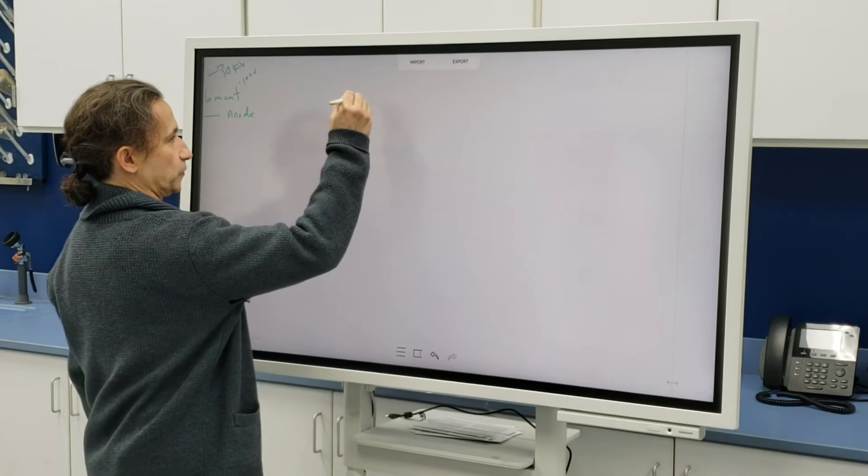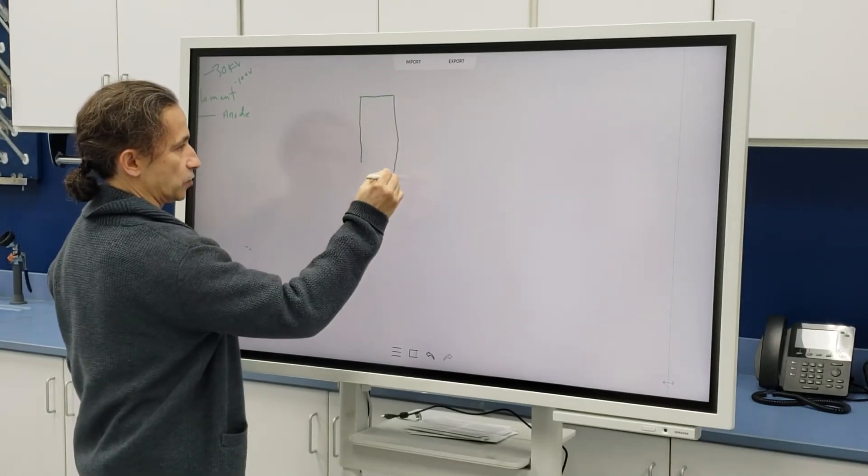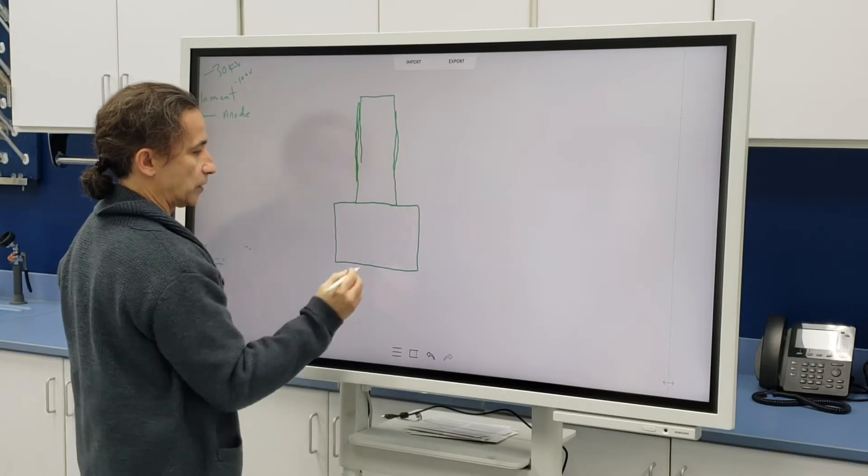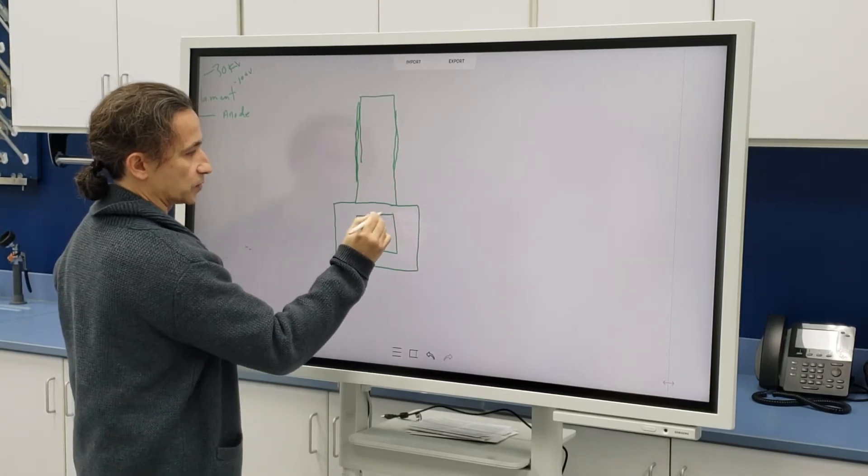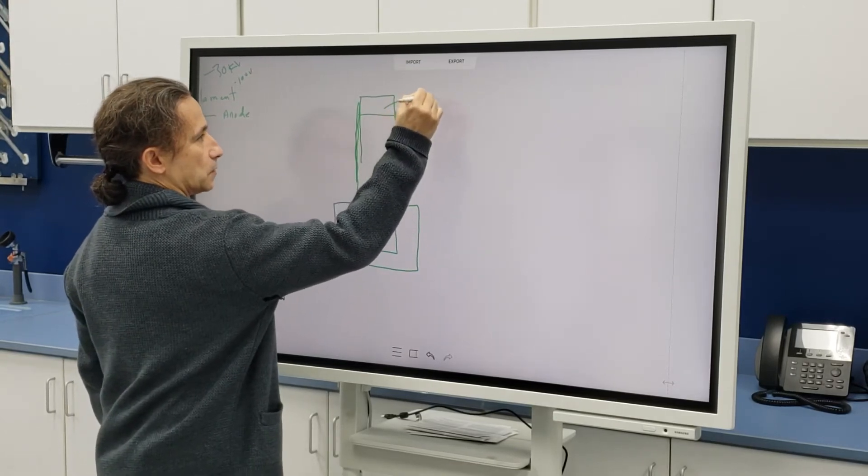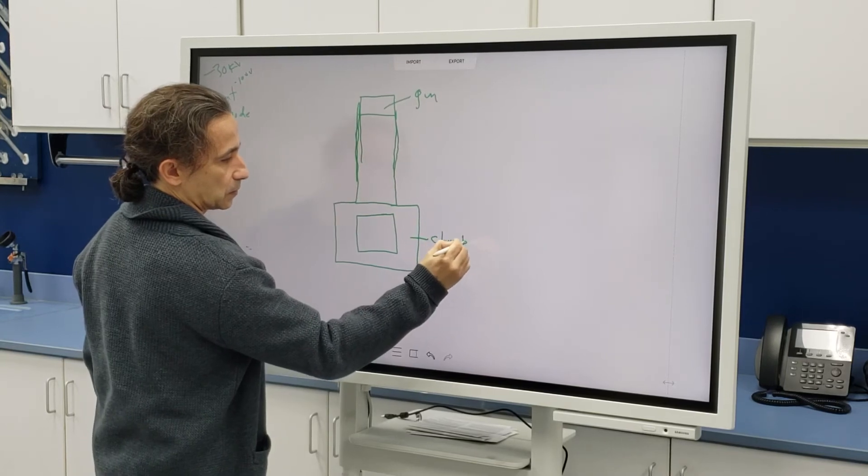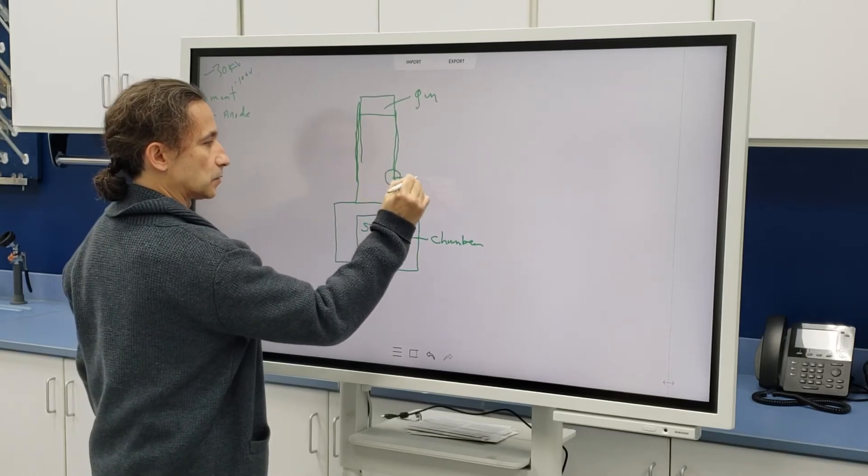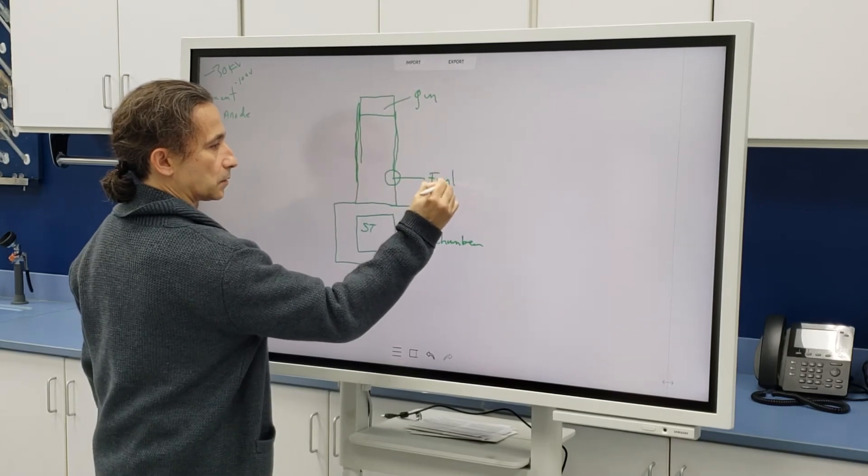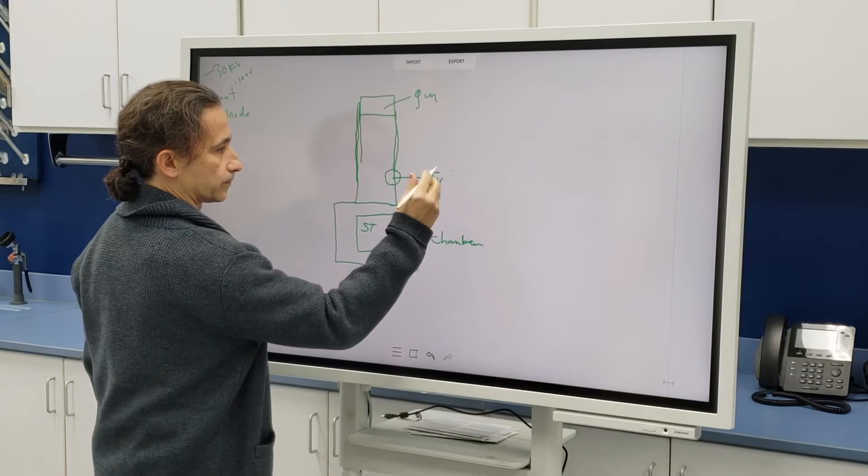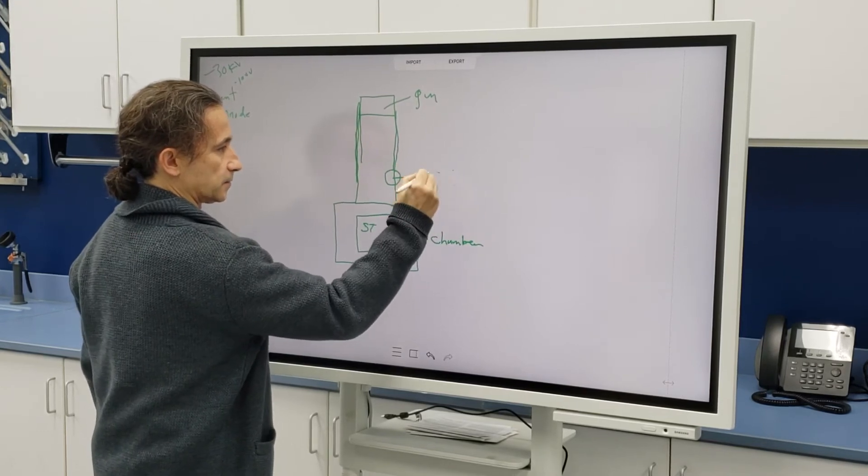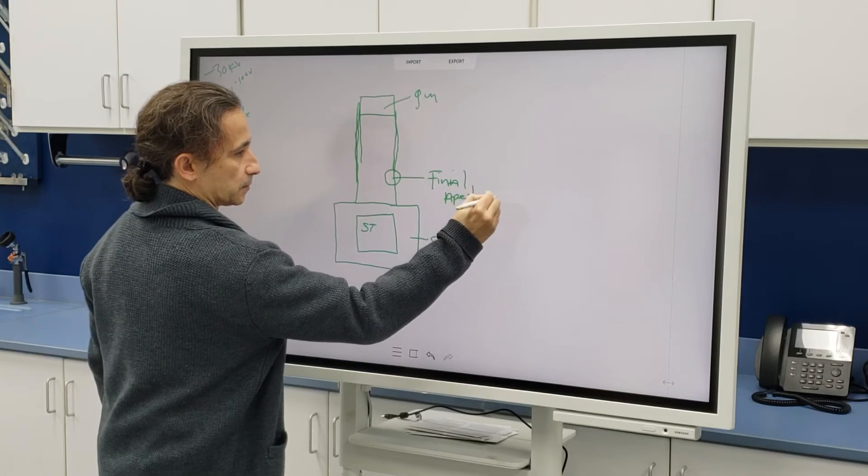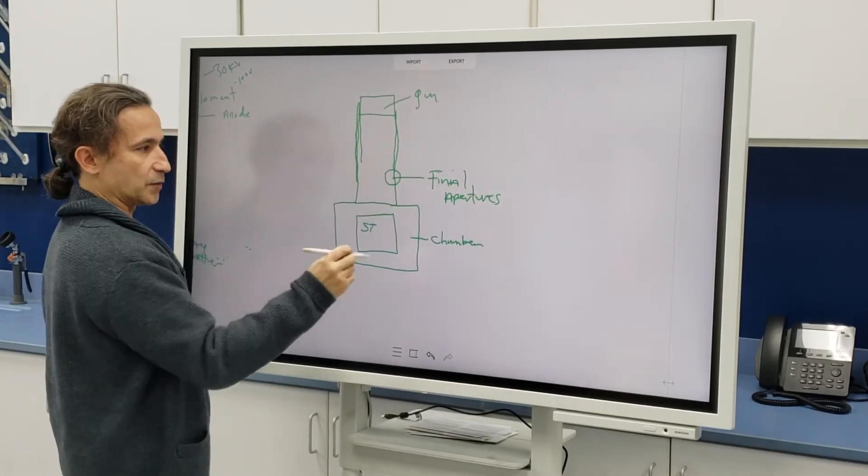So if we were to draw a very rough interpretation of this column, it's a very straight piece. This would be your stage door that opens. This would be your gun section up here. Chamber. Stage. What also is on this column is the final aperture assembly.